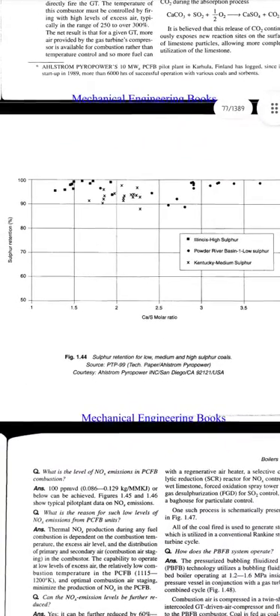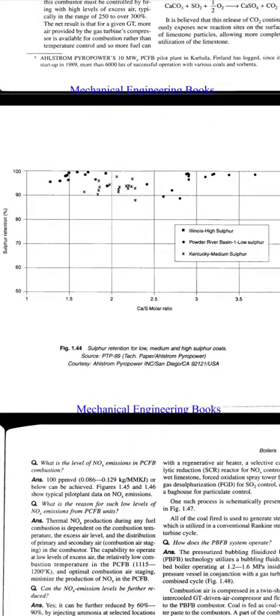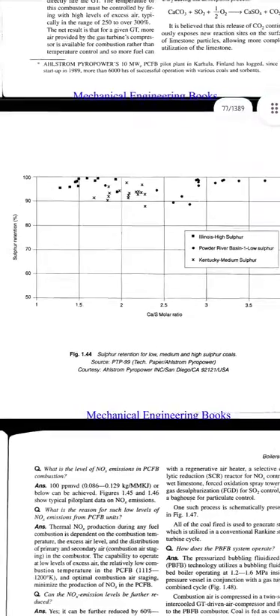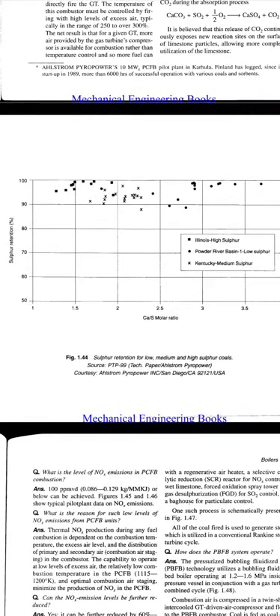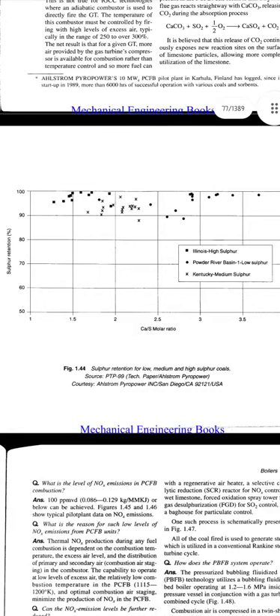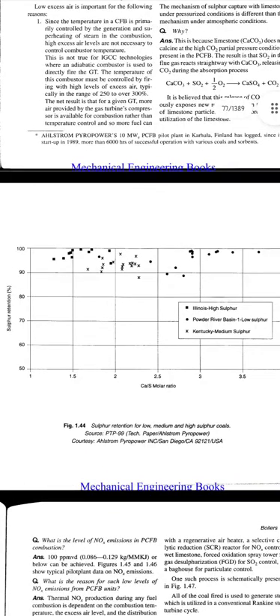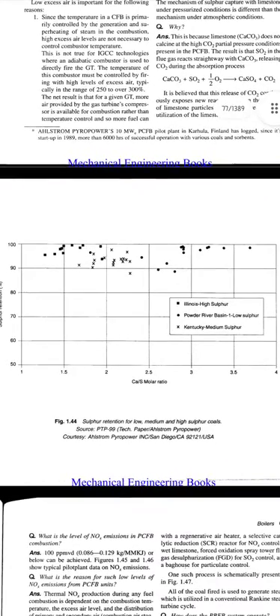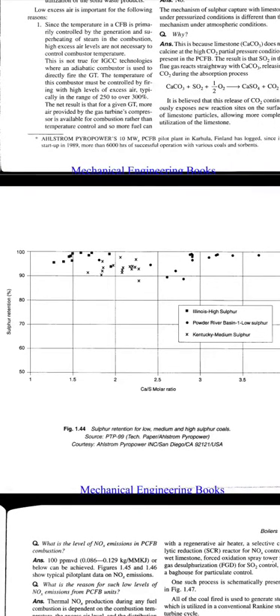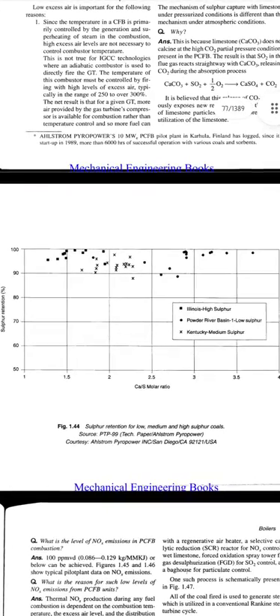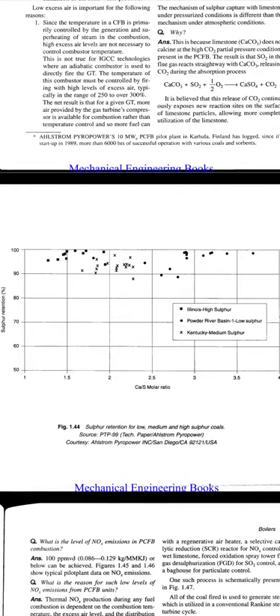Here we can see the sulfur retention graph for low, medium, and high sulfur coals. High sulfur coals are shown as rectangles, low sulfur as circular dots, and medium sulfur (Kentucky) as stars in the diagram. The x-axis is the calcium to sulfur molar ratio and the y-axis is sulfur retention in percentage. High sulfur coals correspond to low calcium-sulfur molar ratios, low sulfur coals to high ratios, and medium sulfur coals to medium ratios.